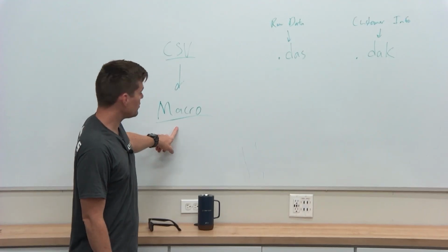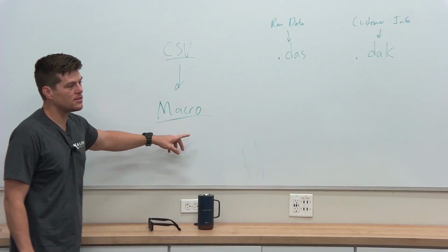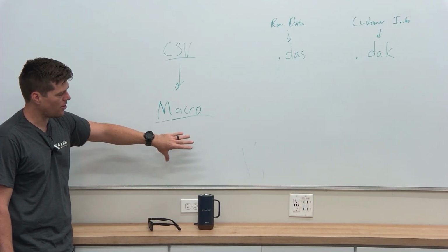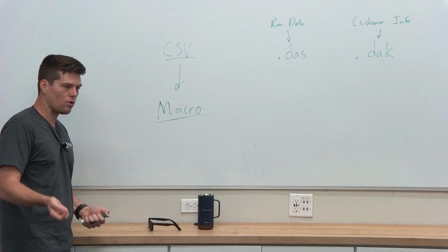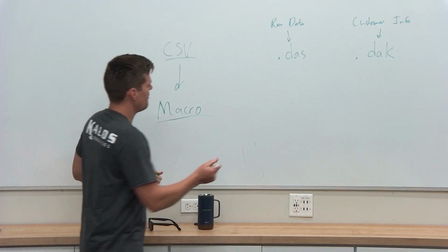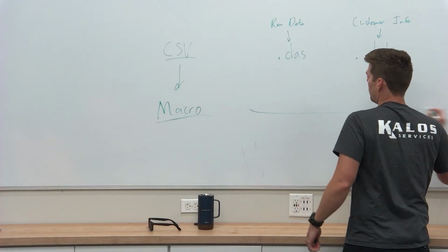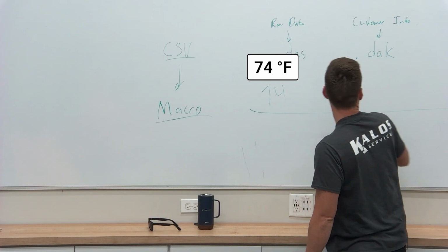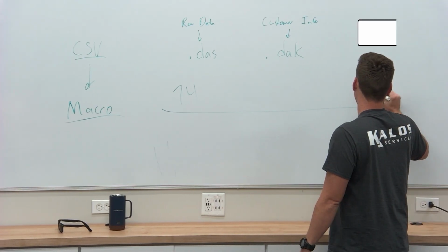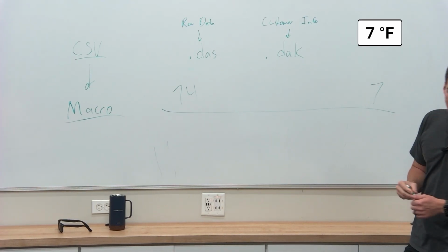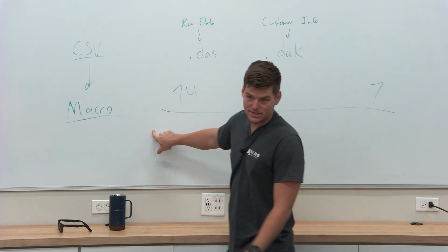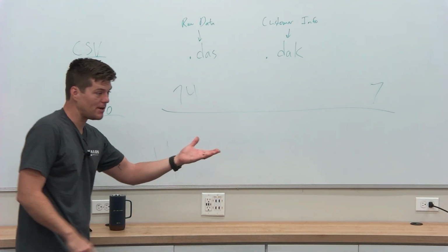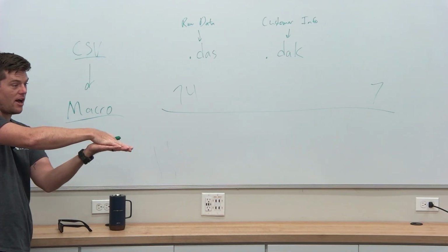This is a learning tool, right? And this is the program that I used when I started that actually made things start clicking for me. They actually showed me the correlation. They showed me, okay, well, from here all the way to here, it's 74 degrees, but over here, it's 7 degrees, right? And so when you look at the macro and you see this, these refrigerant pipes are connected, because it takes the service manual piping diagram and lays numbers on top.